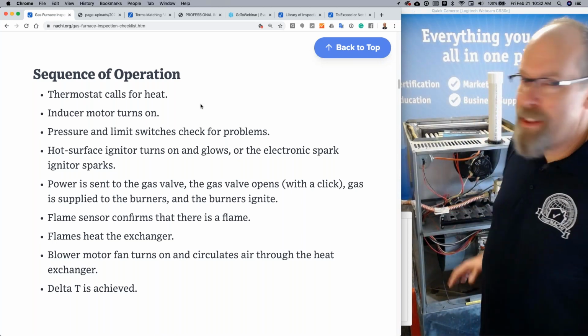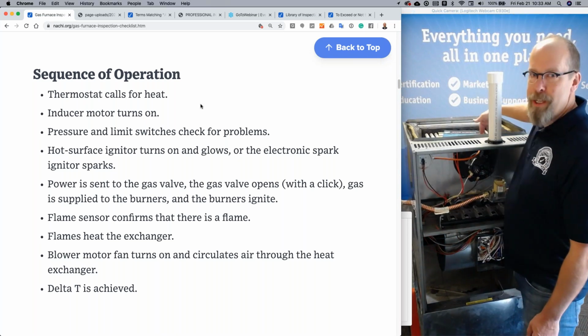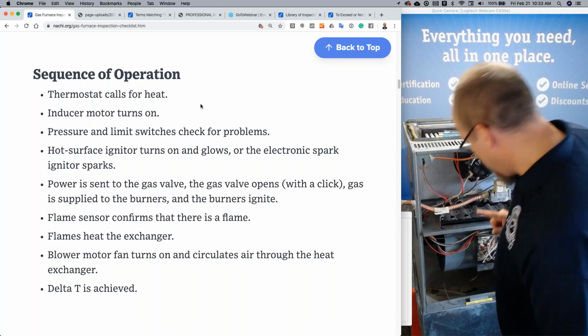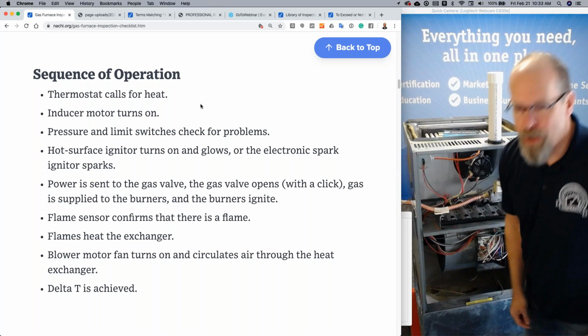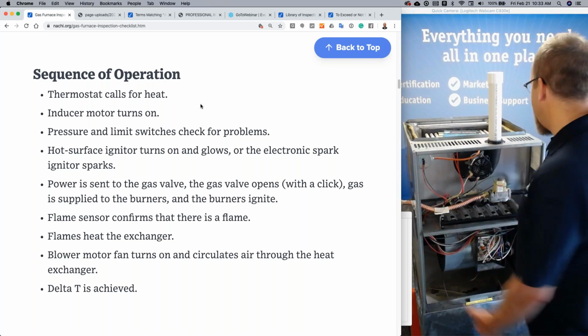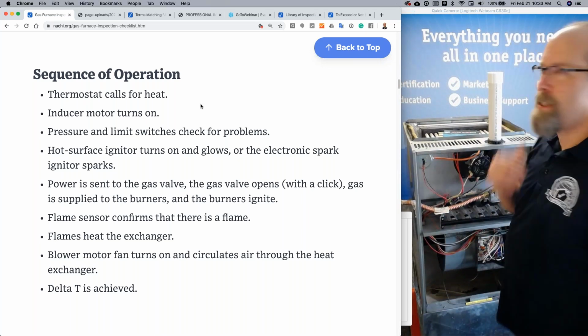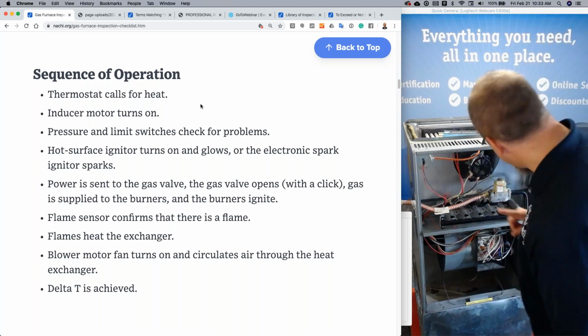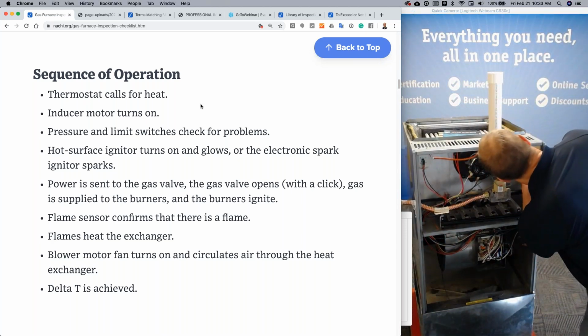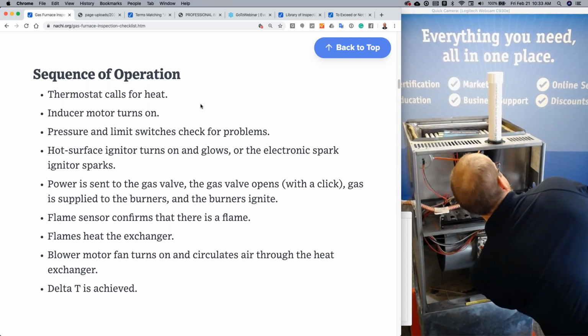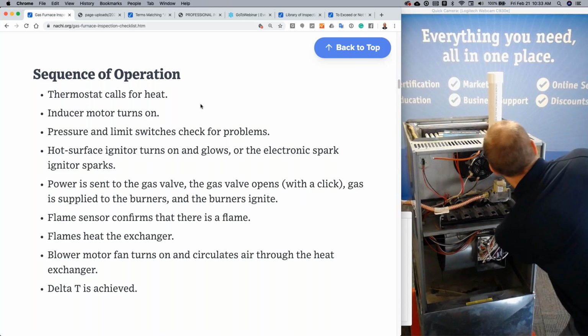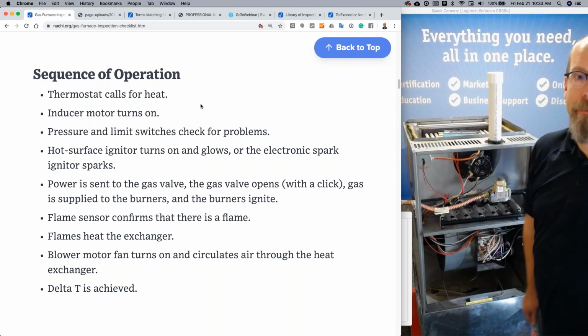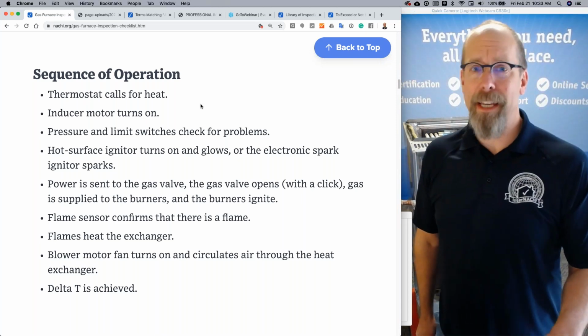The flames heat the heat exchanger, which is here. The blower fan, which is here, turns on and circulates air through the heat exchanger. And a delta T is achieved, which is described on a label on the side of the unit here. It'll say, where is it? Air temperature rise, a minimum and a maximum. So that's the sequence of operation.